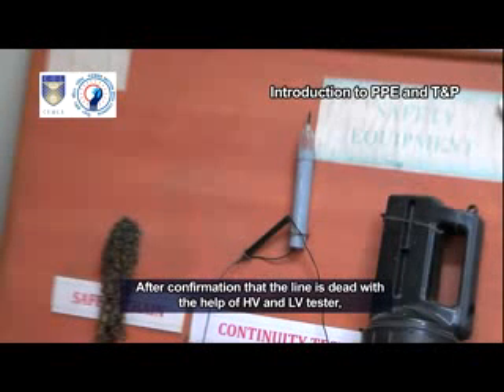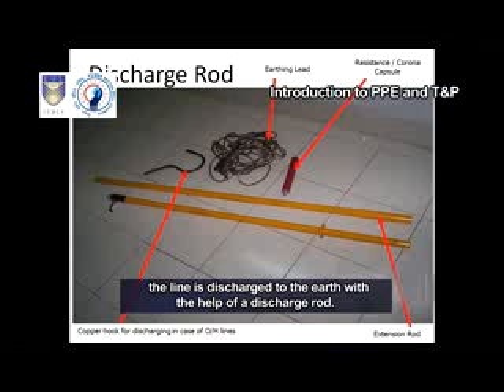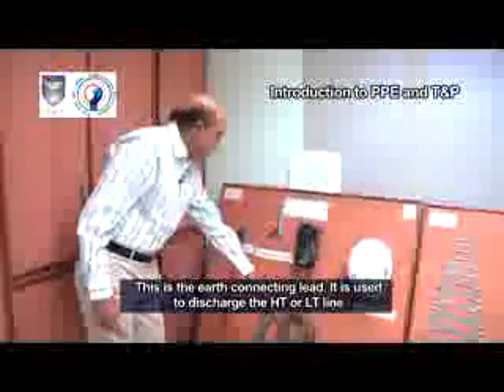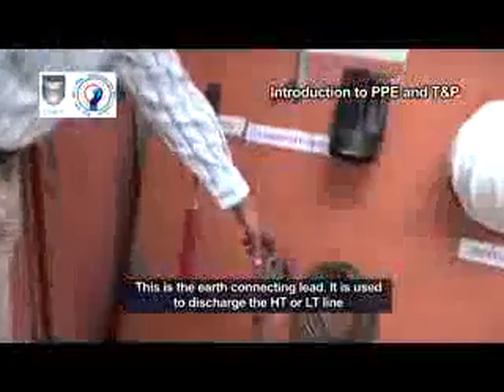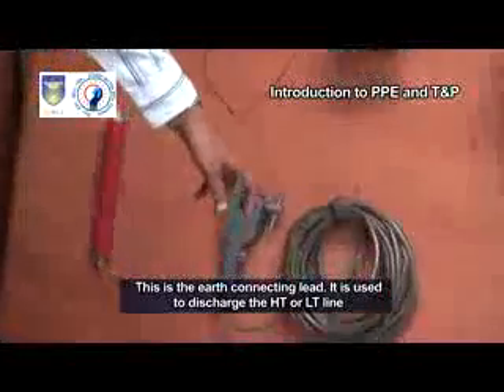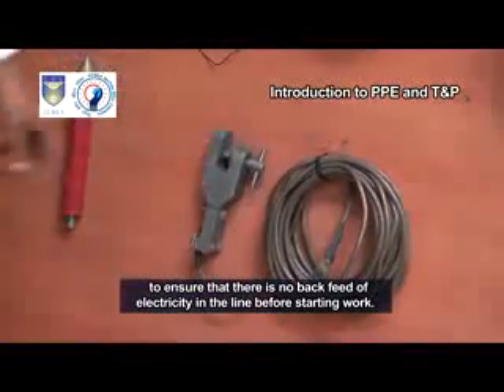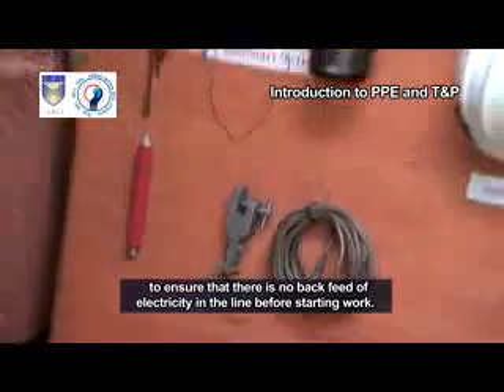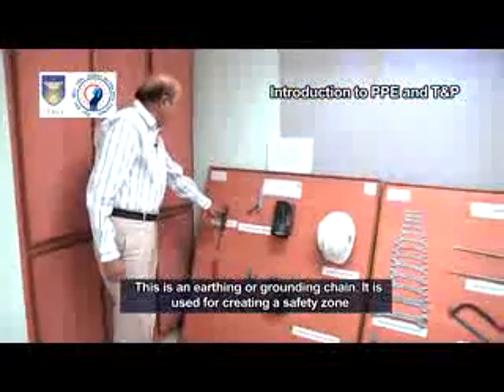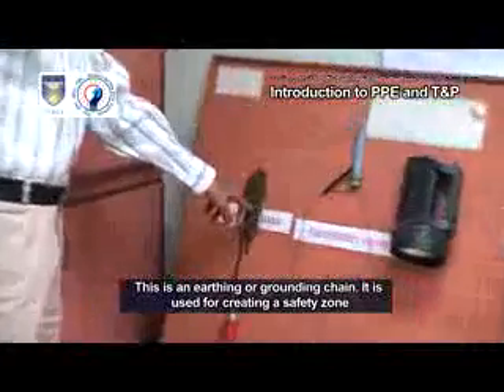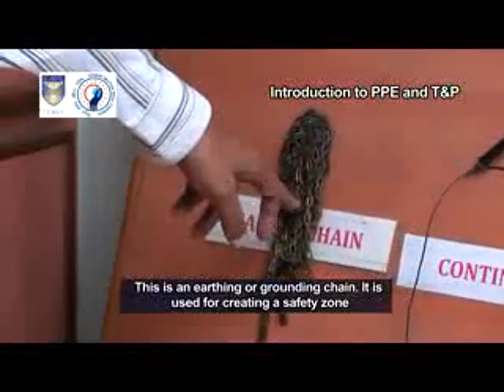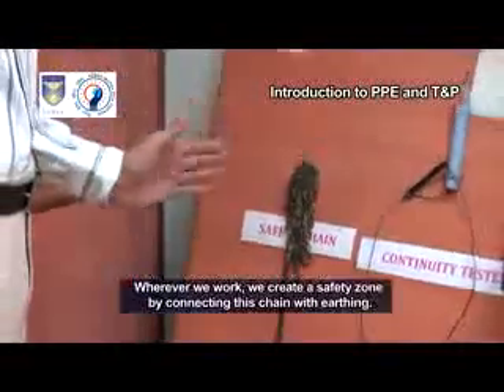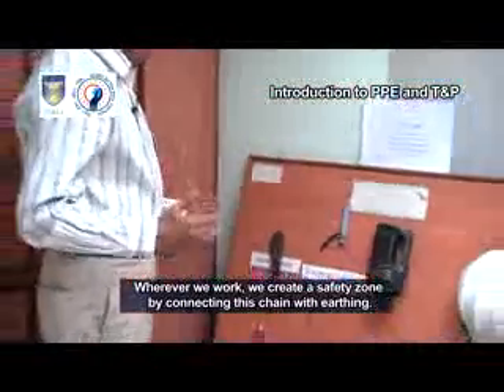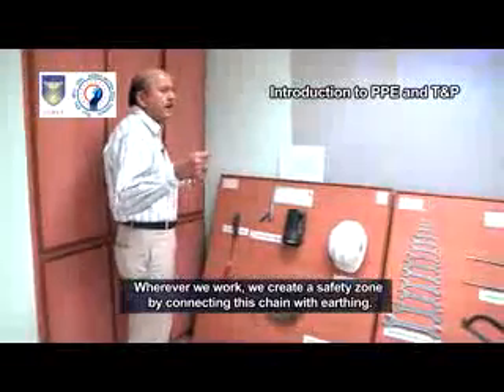After confirmation that the line is dead with the help of the HV and LV tester, the line is discharged to the earth with the help of a discharge rod. This is the earth connecting lead. It is used to discharge the HT or LT line to ensure that there is no backfeed of electricity in the line before starting work. This is an earthing or grounding chain. It is used for creating a safety zone after discharging the line. Wherever we work, we create a safety zone by connecting this chain with earthing.